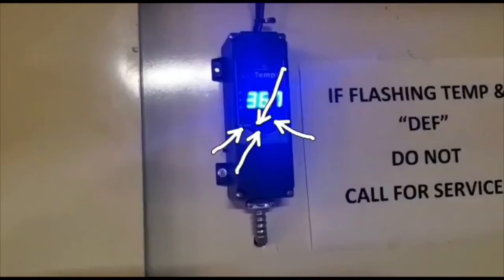So there's a lot of different settings that we can go into on this control to monitor the temperature of the box of the cooler. We can change the defrost times. If we had heat strips on this, we'd control the heat strips for the defrost.